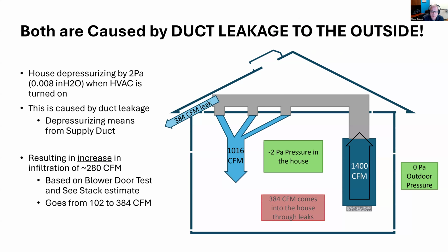So that's just a quick plug. If you don't know about duct leakage to the outside, if you're not doing duct leakage measurements, I recommend you look at that. That's a huge cause of humidity problems, of moisture problems, of comfort problems, and it costs a ton of energy too because you're blowing expensive conditioned air out through the attic. Nobody wants to do that with the expensive air that they paid to cool. So that's all I have for my presentation.